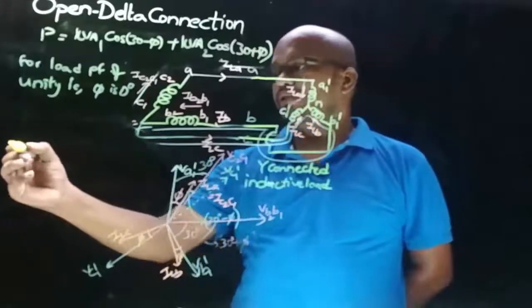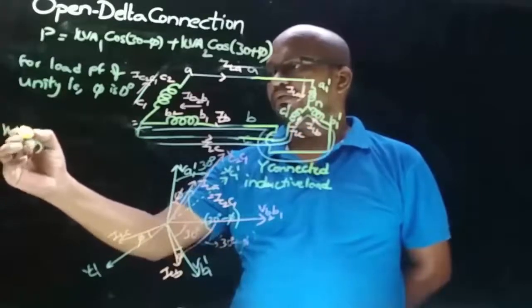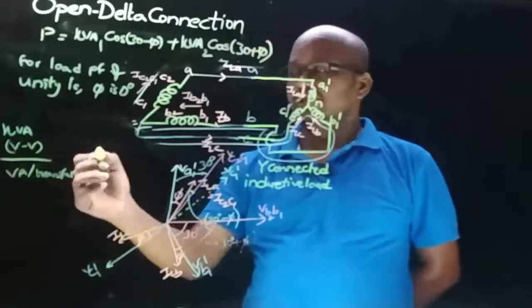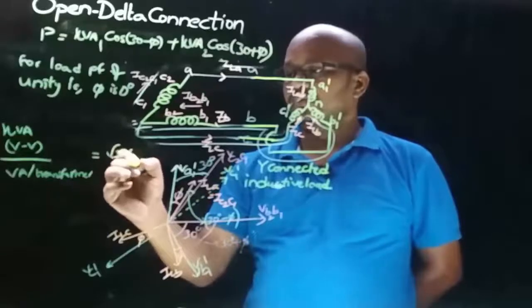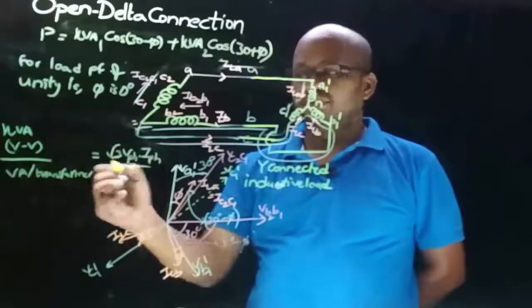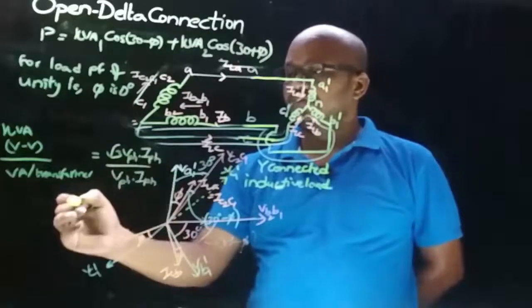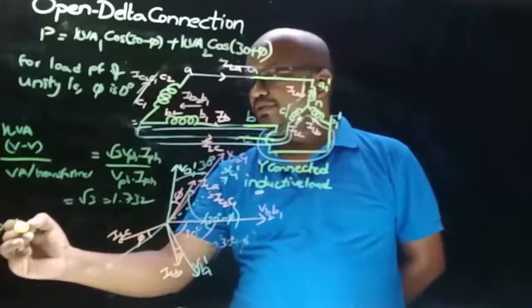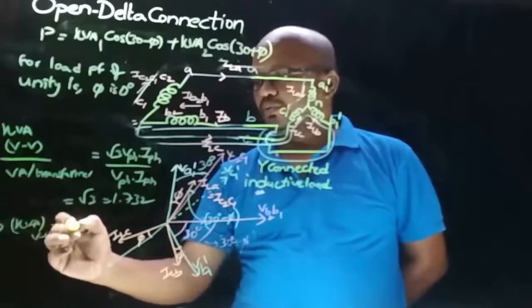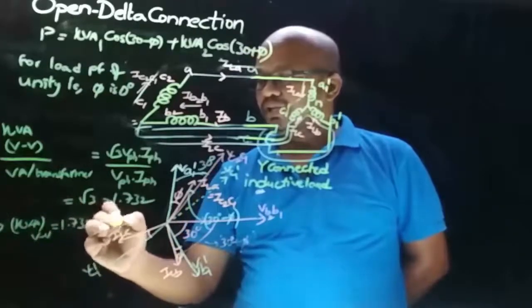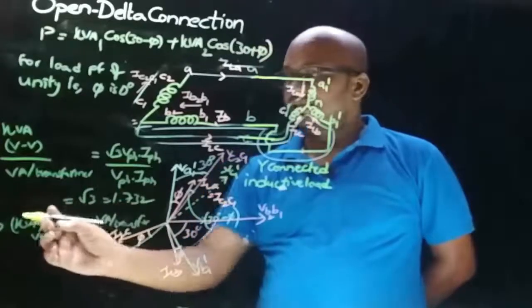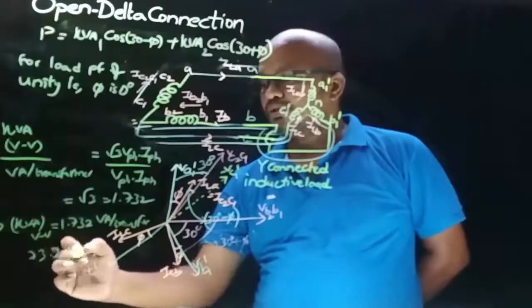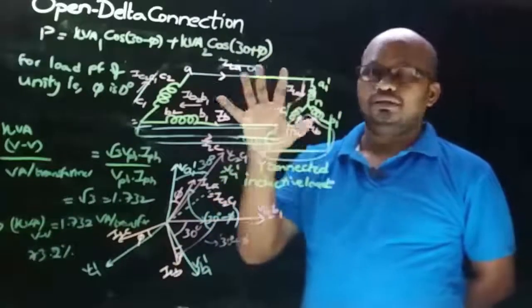Now let's find the ratio of KVA rating of open delta connection to the VA rating of each transformer. This equals root 3 times Vphase times Iphase divided by Vphase times Iphase, which gives root 3 equal to 1.732. Rearranging, KVA rating of open delta connection equals 1.732 times the VA rating of each transformer, which means in open delta connection each transformer is overloaded by 73.2%.